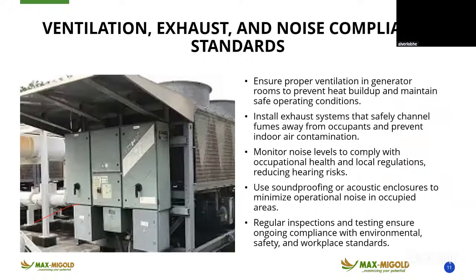Ensure proper ventilation in generator rooms to prevent heat buildup and maintain safe operating conditions. If there is a feedback of heat into the engine room, it will lead to overheating. The generator will keep breaking down and the engine will start knocking. You spend more on overhauling. Ensure you do what you are meant to do: proper ventilation that takes heat out of the engine room.